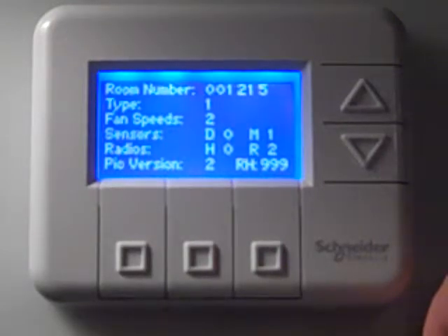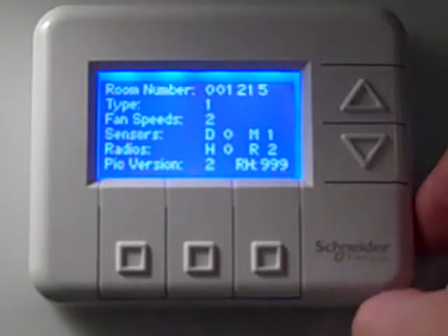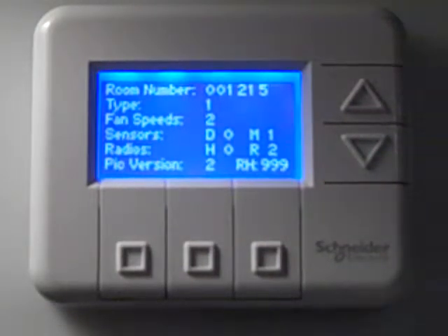That would explain my issue, that anything that's been programmed to this thermostat stays with it. So swapping thermostats around room to room without changing the appropriate radios with them is a number one indicator of a major problem that will show up as chronic device issues, not communicating.